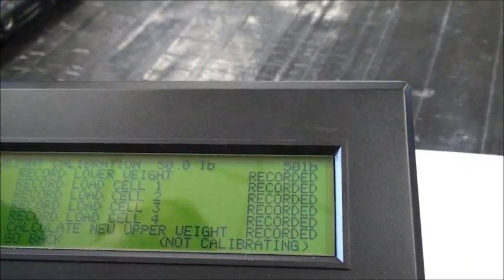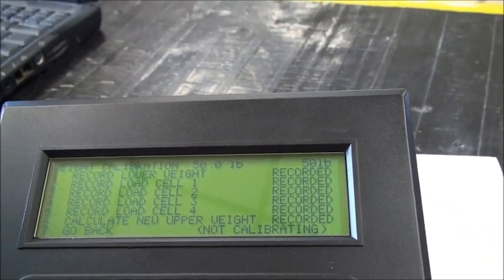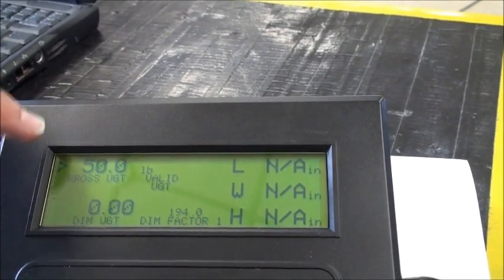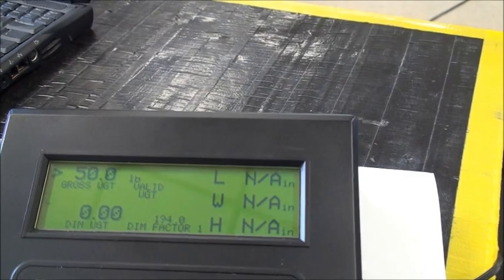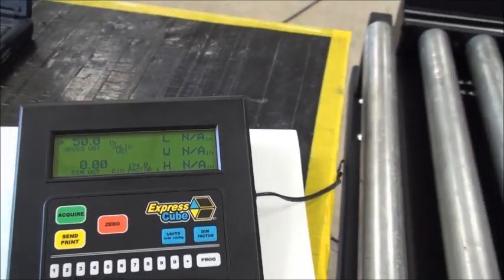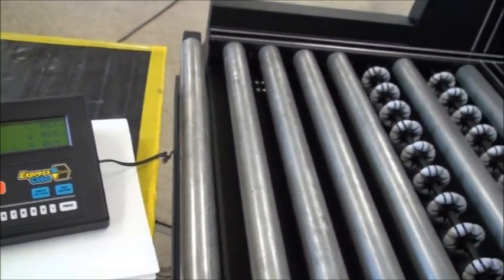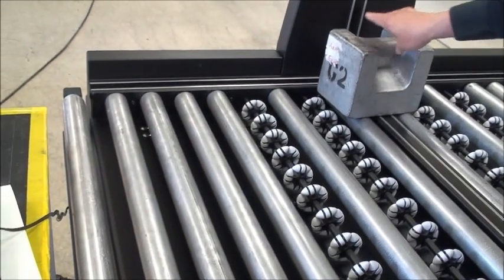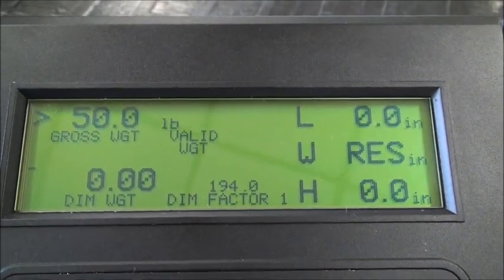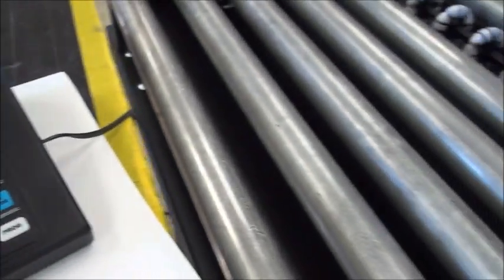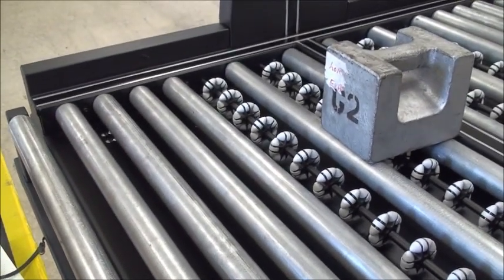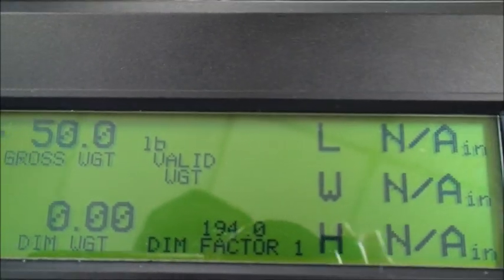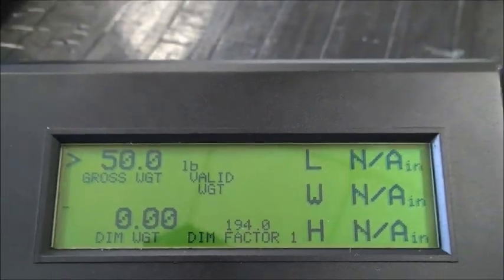Now I'm going to jump out by pressing the prog key because it makes it easier to see the weight. And you'll see the 50.0, which is of course my calibrated weight. I can verify, because no matter where I move this onto the table, it will always show the 50.0. You can verify it because no matter where you put it, it will calculate everything out using the 4 load cells and always come up again. You'll see the 50.0. So that's how we do the calibration on the weight.